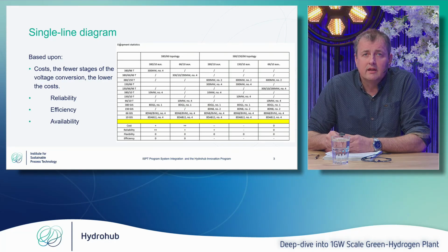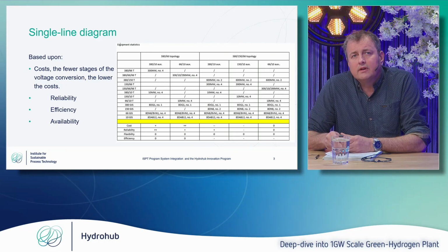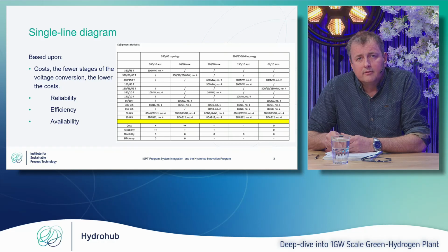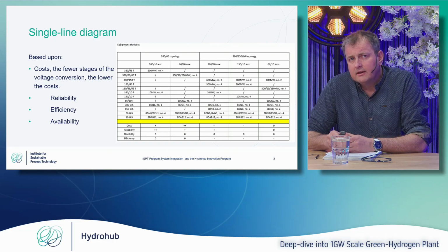Transformers cost a lot of money, and each and every transformer has a certain efficiency loss. So you really need to minimize this, and that was a basis for the design of the single line diagram. We also looked into reliability: the fewer components, the higher the reliability. And we looked into efficiency, as I just explained. The higher the voltage, the lower the currents, and if the current is lower, you also have less losses.